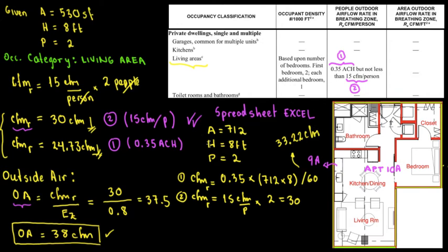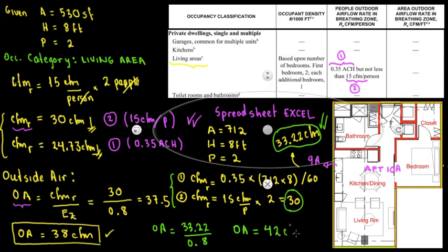From these two in this new example, the highest is based on the 0.35 air changes per hour, which is 33.22. That is higher or greater than 15 CFM per person. So we choose this. In other words, the outside air is going to be 33.22 divided by the distribution effectiveness, 0.8. The outside air would be 33.22 divided by 0.8, that's 41.50. Let's round it up to 42 CFM. So if we do 42 CFM, we're going to comply with the International Mechanical Code.